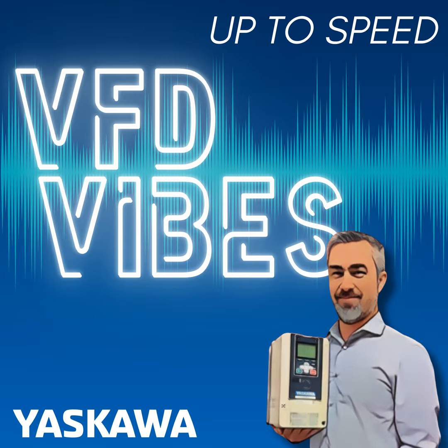If you suspect this is going on, what are some ways to troubleshoot it? Where do you start your investigation? Well, that's a big problem. I'd say that tracing down EMI and electromagnetic noise problems probably accounts for more field time on the part of me and people like me that have gone out to the field than any of these other issues, because they are very troublesome. If you're facing a panel, you've got wires and wireways, and they're all pasted in there together, and it's really hard to tell what goes where. And generally, troubleshooting an EMI problem usually involves having to pick apart and find out where wire 103 goes.